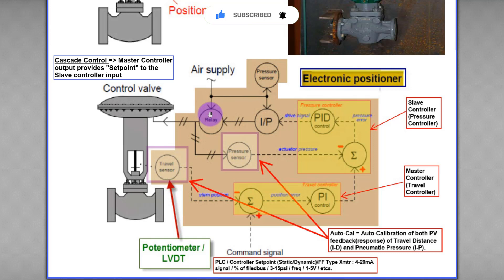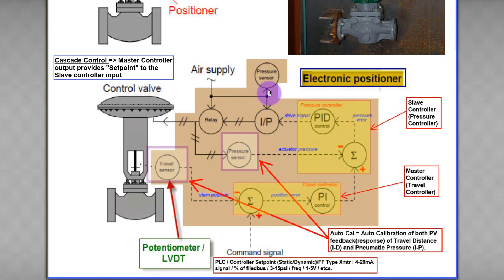Note that there are two pressure sensors located inside the positioner itself. One pressure sensor measures the total incoming pneumatic air pressure, while the other pressure sensor measures the output pneumatic air pressure supplied to the actuator or control valve.